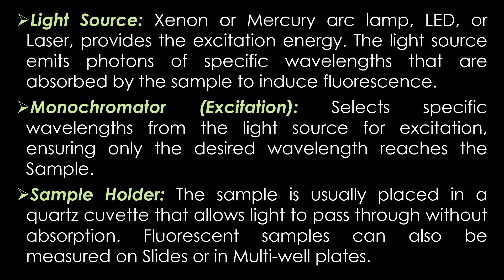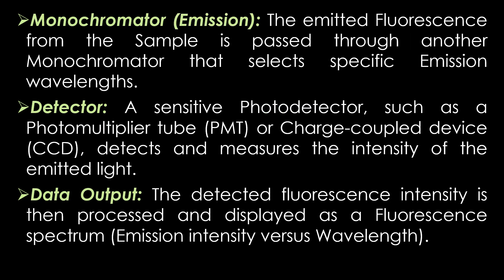The excitation monochromator selects specific wavelengths from the light source for excitation, ensuring only the desired wavelength reaches the sample. The sample is usually placed in a quartz cuvette that allows light to pass through without absorption. Fluorescent samples can also be measured on slides or in multiwell plates.